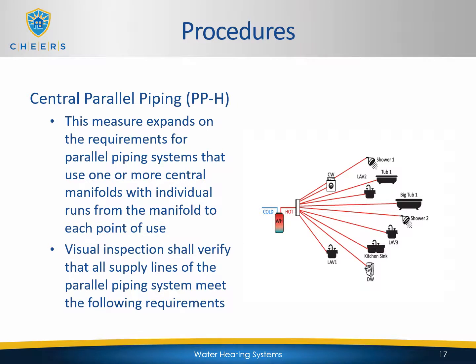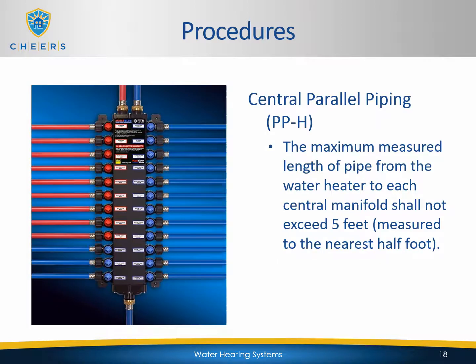For central parallel piping or home run systems, this measure expands on the requirement for parallel piping systems that use one or more central manifolds with individual runs from the manifold to each point of use. Visual inspection shall verify that all supply lines of the parallel piping system meet the following requirements. The maximum measured length of pipe from the water heater to each central manifold shall not exceed 5 feet. That's measured to the nearest half foot.